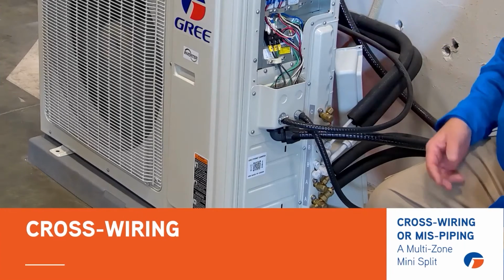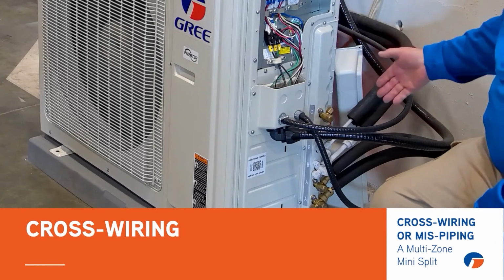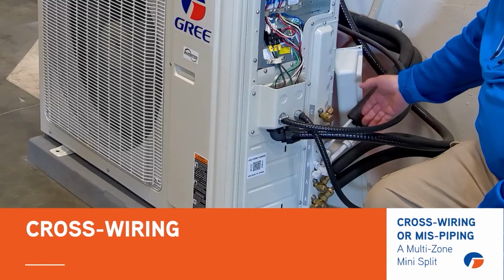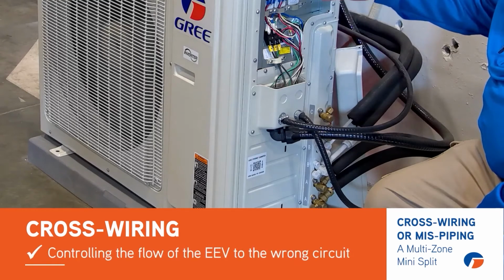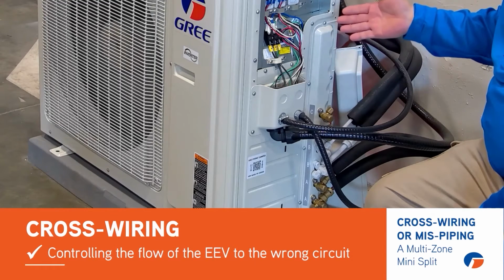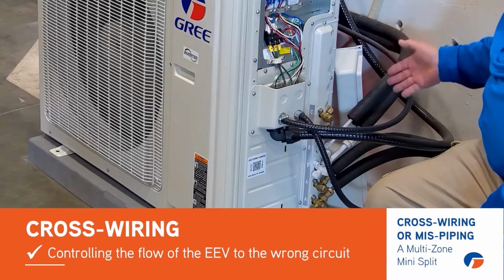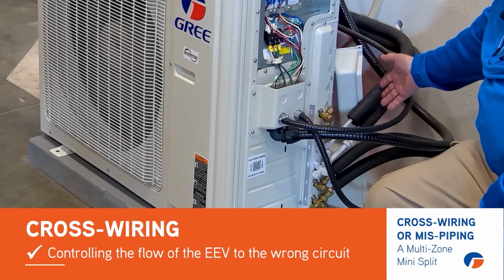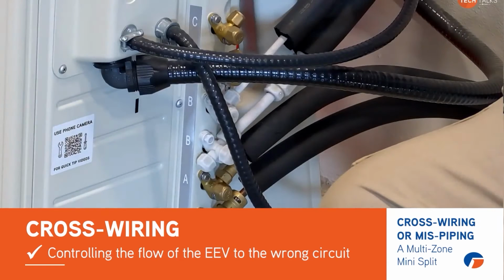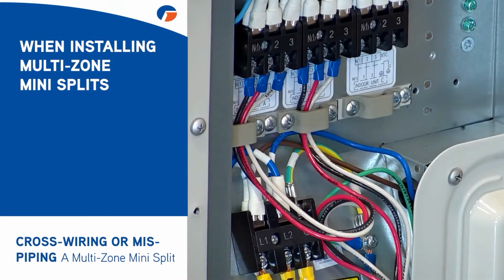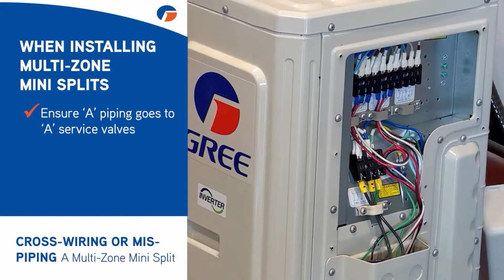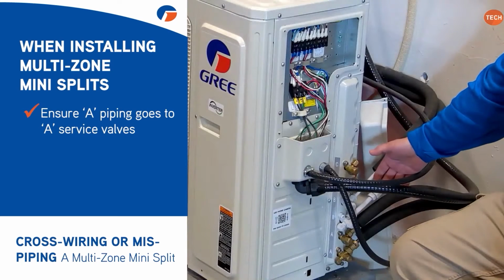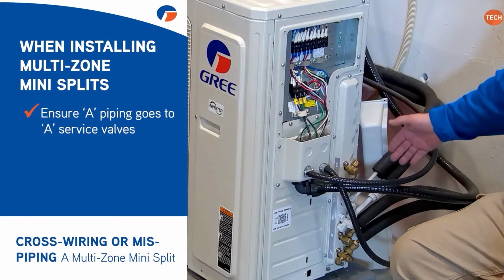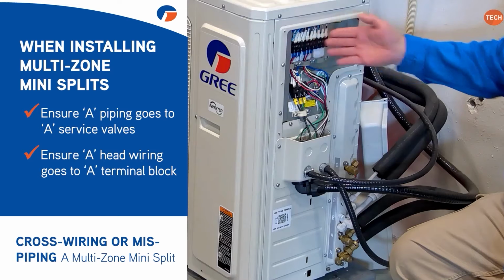So the system that's supposed to be running is the A circuit, but since it's wired to the B circuit, we're controlling the flow on the EEV to the wrong circuit. So therefore, on this B circuit that's not supposed to be running, we have no airflow, we have no indoor fan, and that's why the lines are froze up. So when you're installing these systems, you need to be very careful and make sure your piping from your A circuit goes to the A service valves, and then your wiring from that head goes to the A terminal block.